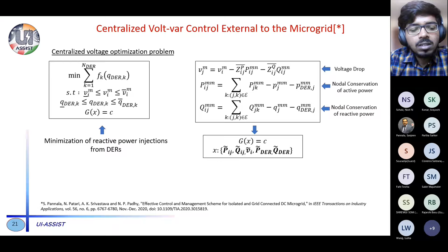Once we have the power system equations, what are the constraints that we have? The constraints are the voltage constraints and reactive power constraints. We have not involved active power constraints from the microgrid, because we are saying that the microgrid will only help in voltage control by exchanging some reactive power. So the voltage in each phase of the network is bounded by an upper limit of 1.05 pu and a lower limit of 0.95 pu, and the microgrid reactive power exchange is also bounded by some upper and lower limits. And then ultimately we have power flow equations. We have already done this work and it has been published. So once we are done with the controls internal to the microgrid, we are thinking of using or comparing those schemes from a utility perspective.